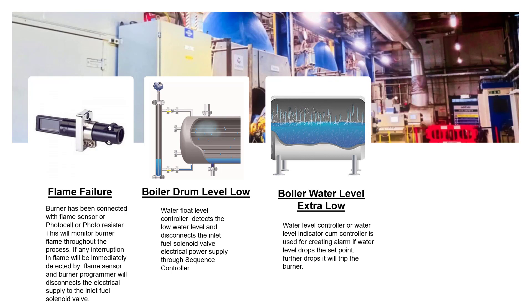Boiler water level extra low: a water level controller or water level indicator cum controller is used for creating an alarm. If the water level drops to the set point and further drops, it will trip the burner.